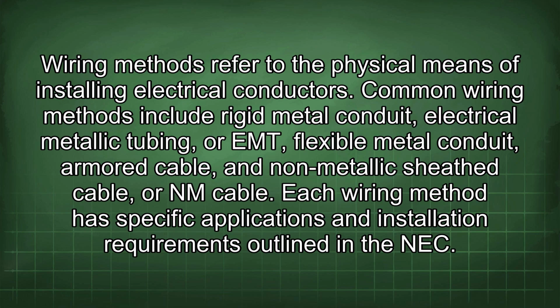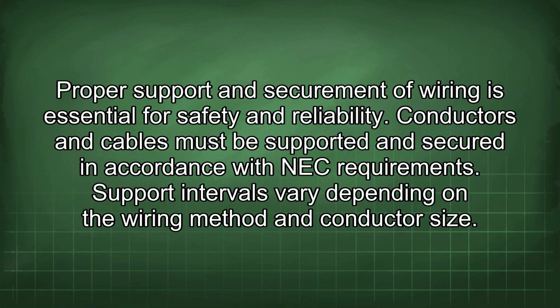Wiring methods refer to the physical means of installing electrical conductors. Common wiring methods include rigid metal conduit, electrical metallic tubing, flexible metal conduit, armored cable, and non-metallic sheath cable, or NM cable. Each wiring method has specific applications and installation requirements outlined in the NEC. Proper support and securement of wiring is essential for safety and reliability. Conductors and cables must be supported and secured in accordance with the NEC requirements. Support intervals vary depending on the wiring method and conductor size.